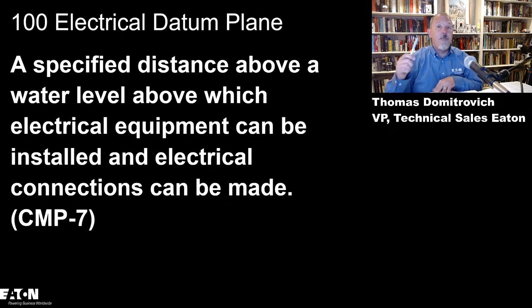The electrical datum plane is a specific distance above a water level, above which electrical equipment can be installed and electrical connections can be made. We want to be above the water level. On a floating dock, you're sure to be above water level because you're floating. If you're on a fixed pier, that means you're fixed in place, not raising and lowering based upon water levels. Things on shore, the ground does not go up and down based upon water level. The water level encroaches on the earth and pulls away.